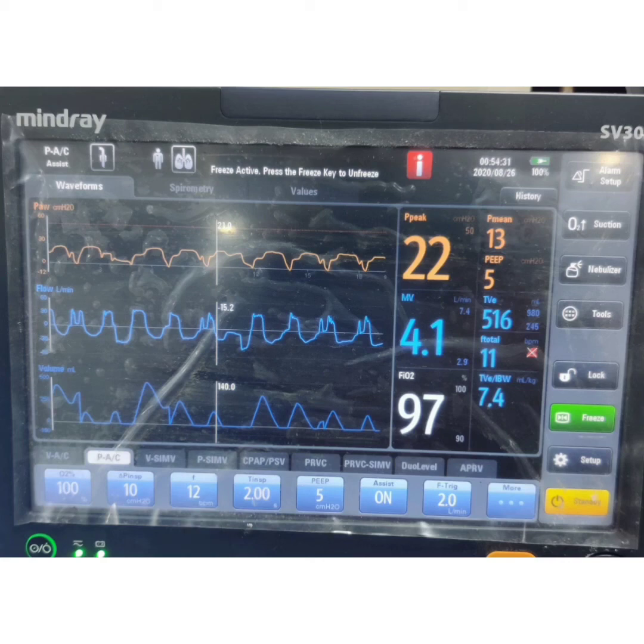As every breath is an assisted breath only, the patient's spontaneous frequency must have been more than 12. The next mode is intermittent mandatory ventilation, IMV. IMV is nothing but mandatory breaths together with spontaneous breaths. Mandatory breaths are given intermittently, allowing the patient to take spontaneous breaths in between. These spontaneous breaths are not supported by the ventilator.